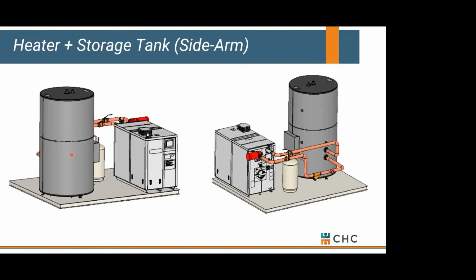I know I've said this before. I'll say it one more time. Just be careful. We have a lot of individuals, engineers, contractors, personnel that will look at this application and say, we've got a boiler serving a storage tank. Be careful with that, because anytime we're directly heating domestic water, technically it's a water heater. So this is a water heater that is serving a storage tank. Okay, that gets confused a lot and creates a lot of pain points. If you see a lot of copper pipe, yeah, you might want to check it out. Probably a good indication you've got a water heater application.